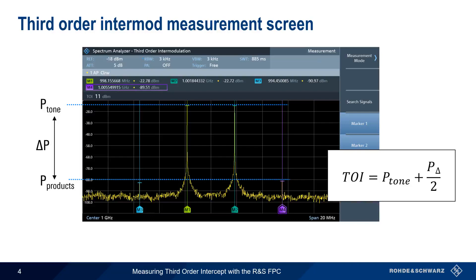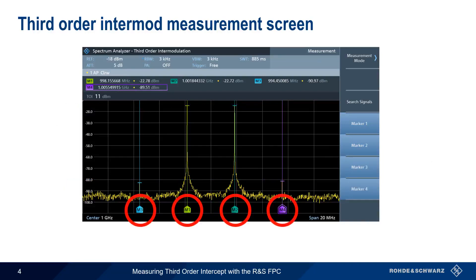The FPC does this automatically by placing four markers — two on the fundamentals and two on the detected third-order products — and then calculating the third-order intercept.